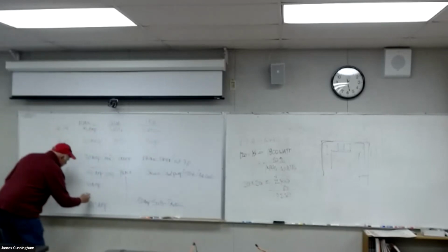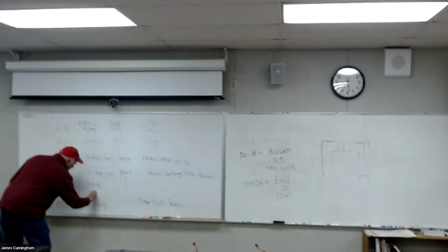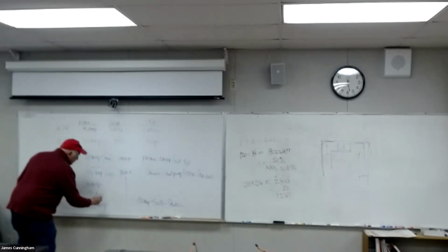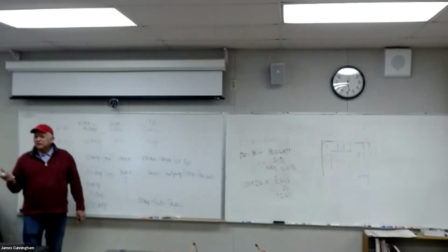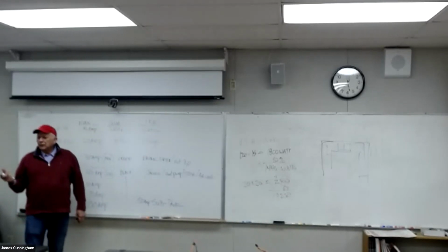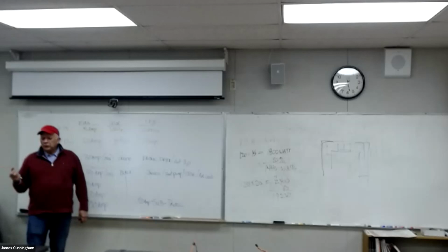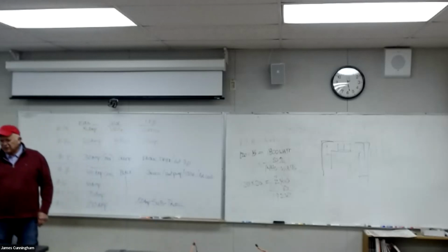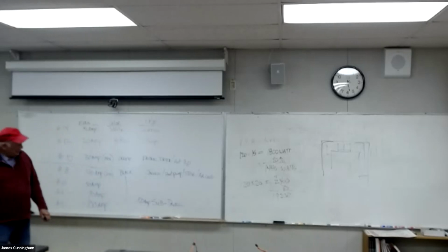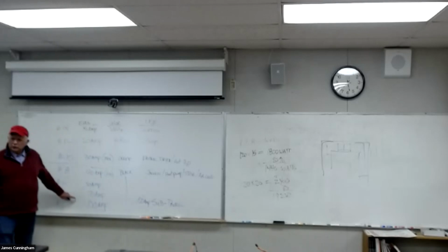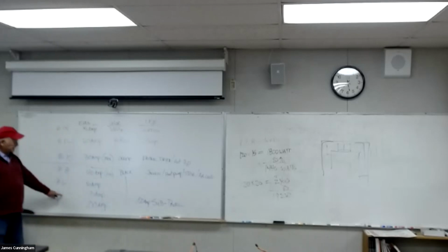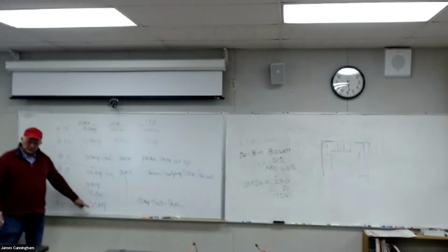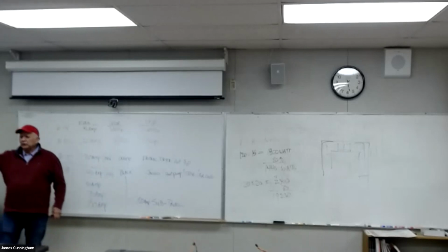could be used, this is like a 70 amp. It could be used for a sub panel, but the new code requires the minimum size sub panel to be a 100 amp. So it's kind of like you're not really using this much anymore. You can use the number 4 sometimes for a 100 amp sub panel, but it would have to be a very short distance, really short distance.